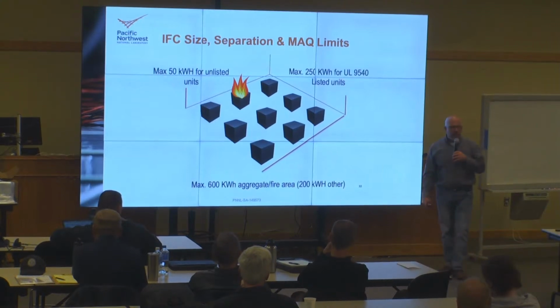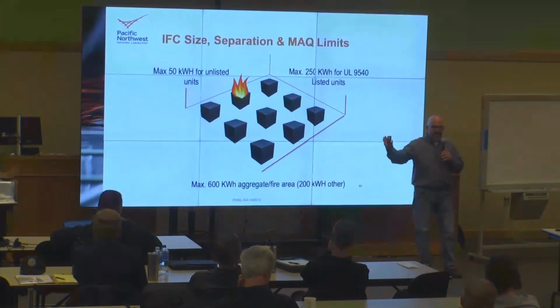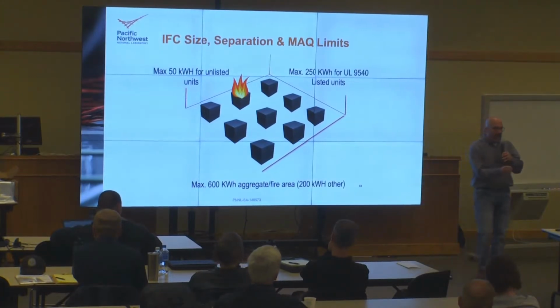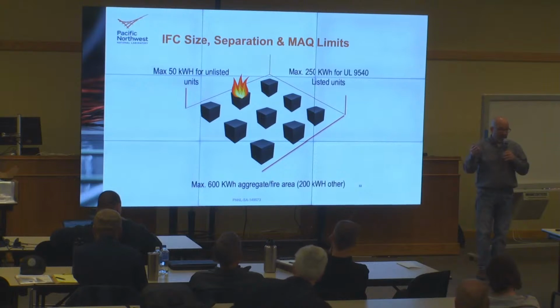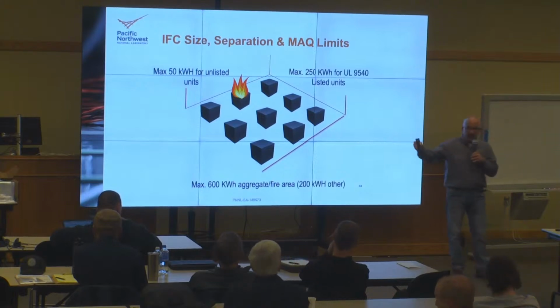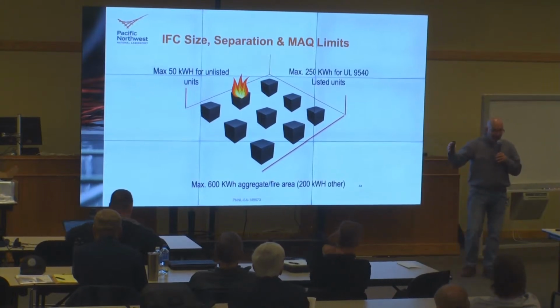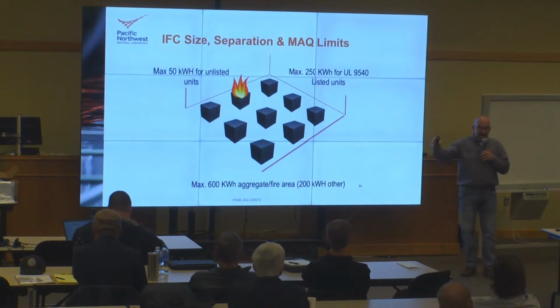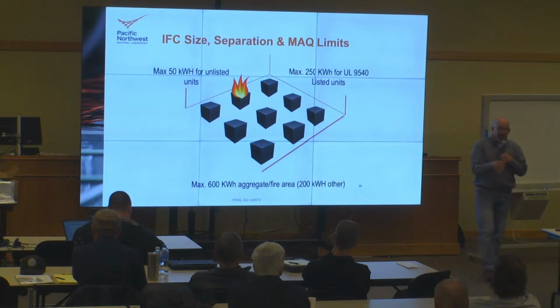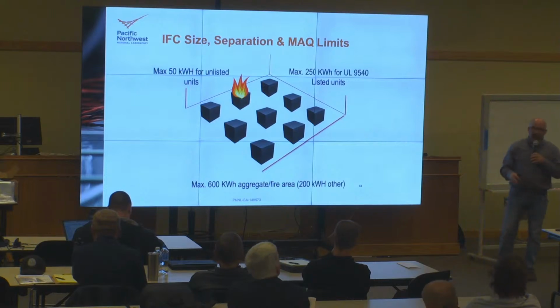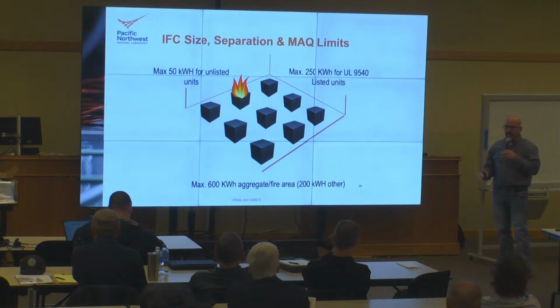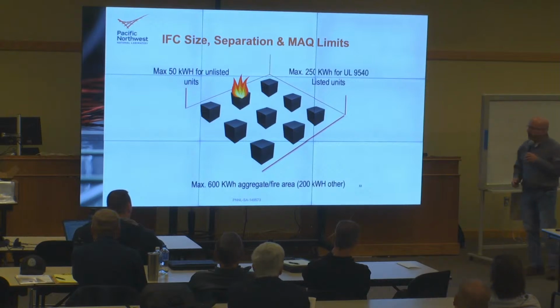So what's happening now with that 9540A test is it's becoming more and more required on every system because they're all bigger than 50 kilowatt-hours, they're all sandwiched next to each other. My hope is that 9540A kind of goes away and all the requirements for the test just get lumped right into the 9540 listing, and every battery has to go through that. Manufacturers probably hate me for saying that because it's really expensive, but we've learned a lot about battery design by doing that.